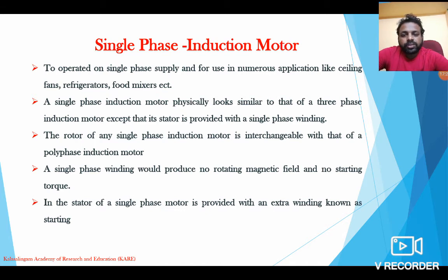And a single phase induction motor physically looks like a three phase induction motor, except its stator is provided with a single phase winding, right? Just keep in mind, in a single phase induction motor the stator has single phase winding. So the rotor of any single phase induction motor is interchangeable with that of a polyphase induction motor, and a single phase winding would produce no rotating magnetic field and no starting torque. So this is a drawback.